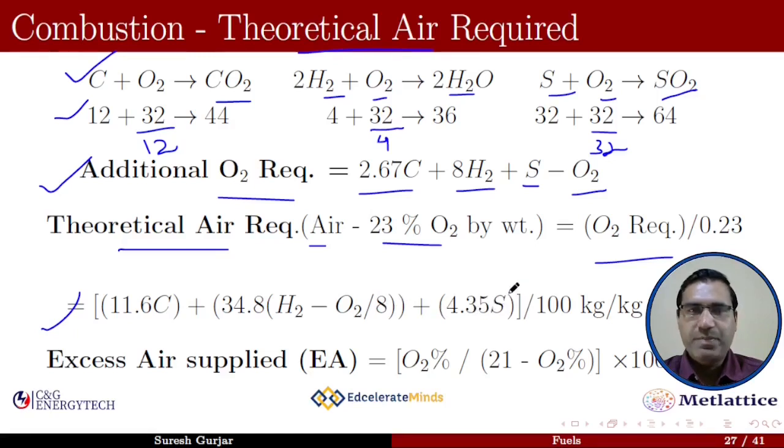Next is the calculation of excess air supplied, which can be calculated with the help of the actual O2 percentage in the flue gas. It is given by O2 percentage divided by 21 minus O2 percentage.